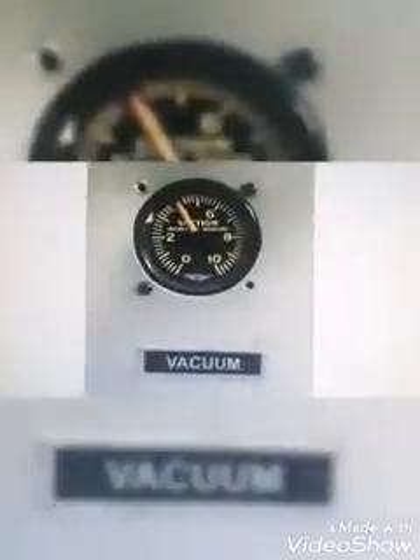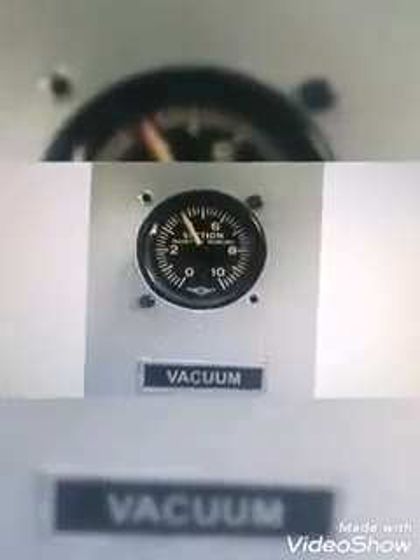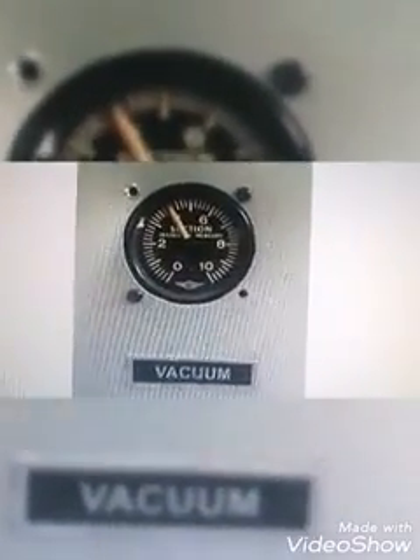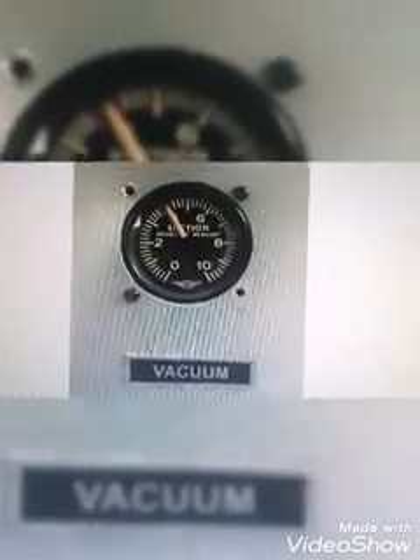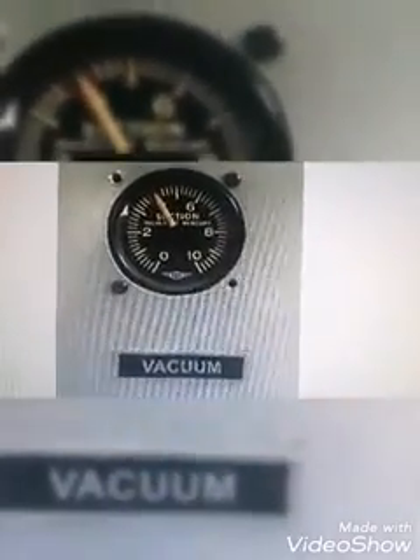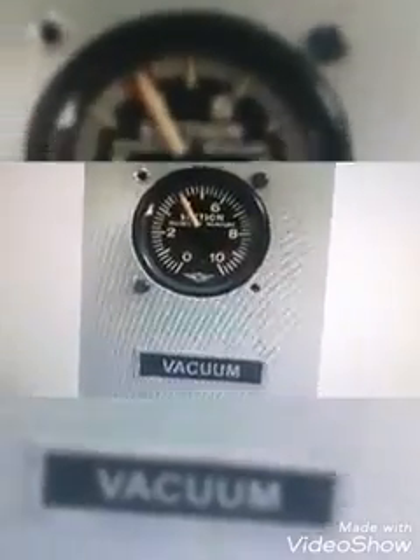When you have a correct measurement in the instrument, the vacuum measurement must be between 4.5 and 5.1. This pressure will be relative to the speed of the gyro. For example, in the instruments, it is possible to observe that the pressure is within the stabilization parameters of the manual.